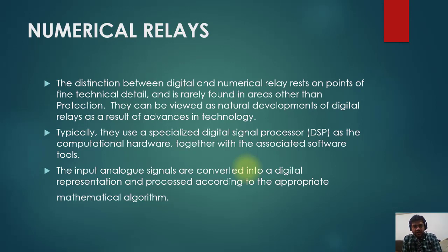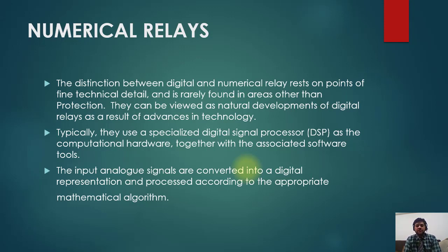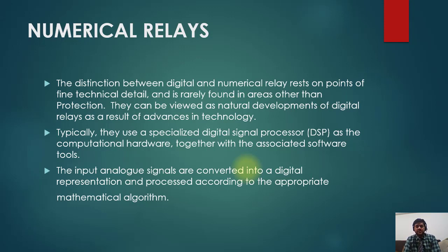The final type we are seeing are numerical relays. The distinction between digital and numerical relays rests on fine technical detail and is rarely found in areas other than protection. They can be viewed as a natural development of digital relays as a result of advances in technology. Typically they use a specialized digital signal processor as computational hardware together with associated software. Analog input signals are converted into digital signals inside the relay and processed using appropriate mathematical algorithms.